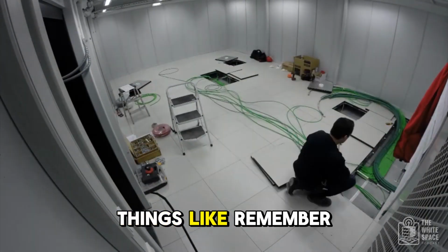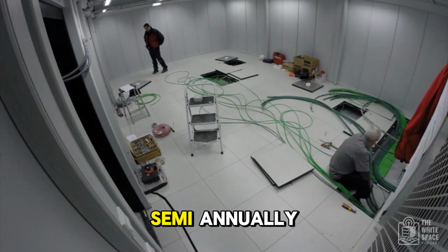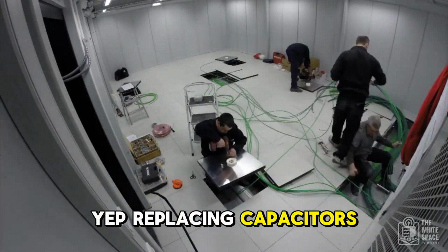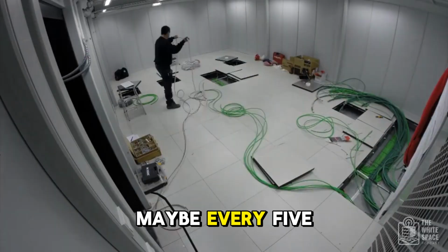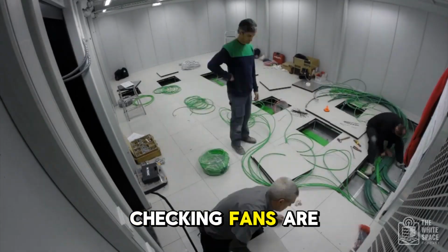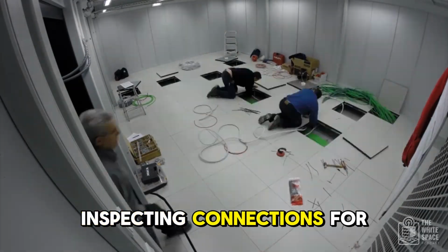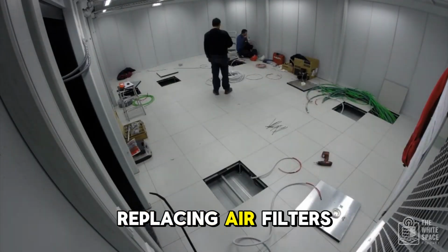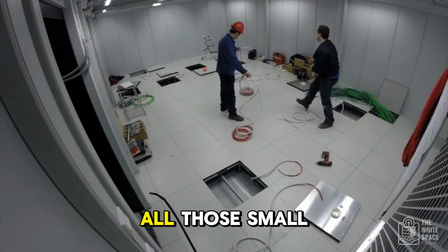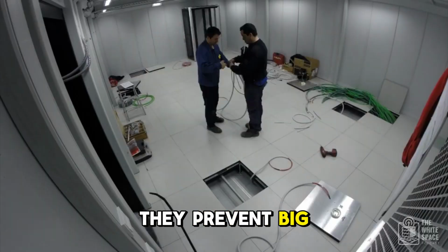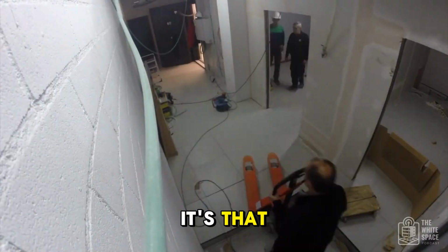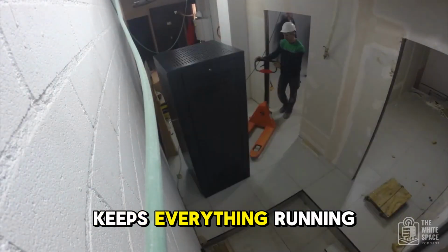We're talking about things like battery checks semi-annually, replacing capacitors in UPS systems maybe every 5 to 7 years, checking that fans are clean and running, inspecting connections for tightness, and replacing air filters monthly to stop overheating. All those small things add up - they prevent big, expensive outages. It's that invisible work that keeps everything running smoothly.